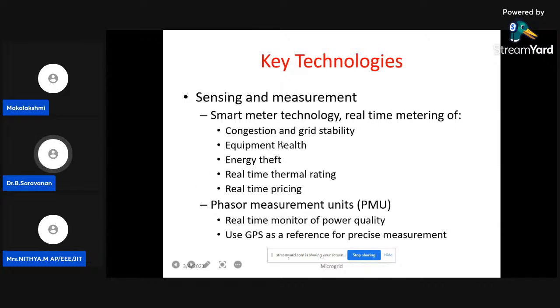Equipment health means checking whether everything is proper. For example, with a transformer, we always monitor the transformer oil, since its lifetime varies based on moisture content. If you test with a gas analyzer, by seeing the gas formation in the oil, we can find what type of fault is there or which component is deteriorating.